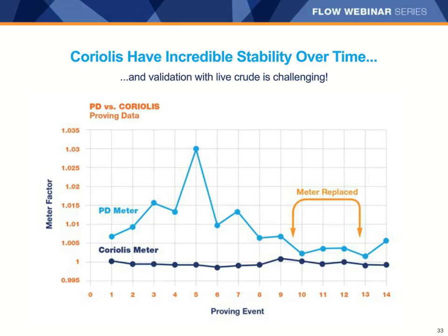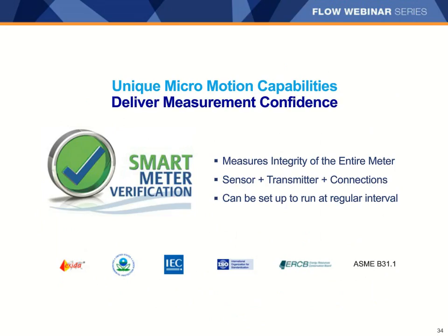Because of that, we've got the smart meter verification that actually verifies the integrity of the entire meter, and it does that for the measurement element through testing tube stiffness. I would encourage you, if you're not familiar with smart meter verification, to again look at the resource list where we have both the white paper and link to video that explain more on exactly how smart meter verification works.